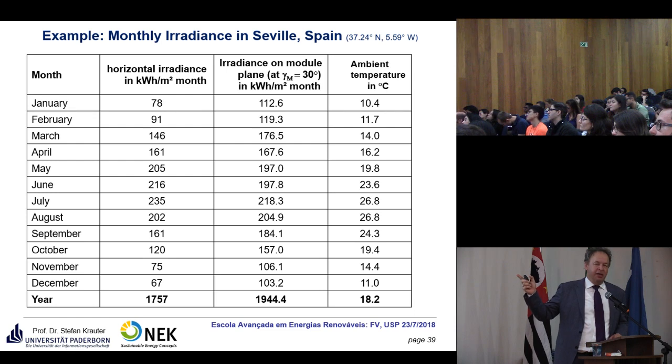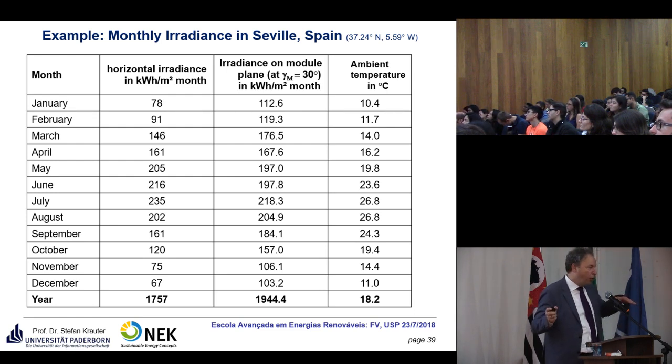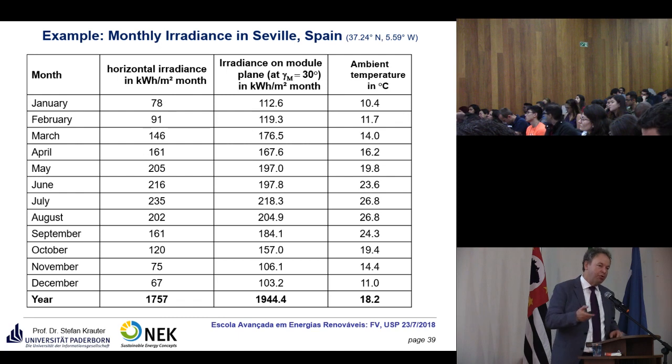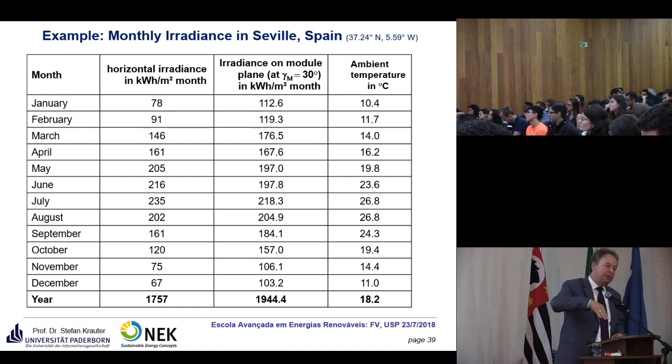Also, if you consider direct radiation, it's better to go more steeply, but if you consider diffuse radiation, then it tends towards horizontal. If you have only diffuse radiation, horizontal is the best position. This is always a compromise. If you want to capture most of the direct radiation, it's better to have a steeper angle, or you want optimization of global radiation, and that includes diffuse radiation.